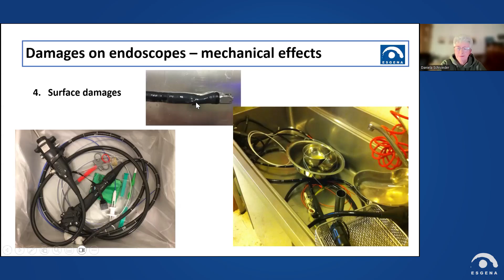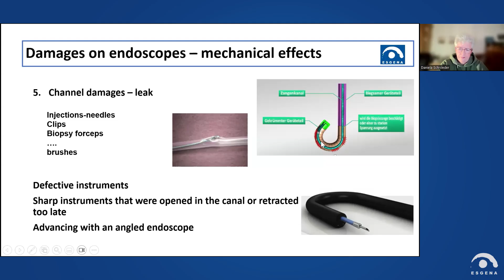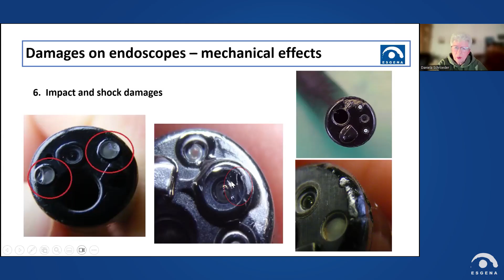Channel damages, which can cause a leak due to defective instruments. For example, we once had a production batch of brushes. They were kinked really soon, and then by withdrawing, they perforated the entire working channel. Sharp instruments that were opened too early or retracted too late, or advanced by pushing with force against the resistance of the angled endoscope, can cause damages and leaks. Even with shock or impact damages, here you can see that we have some broken parts on it. Even this endoscope will work properly. Maybe you have some cracks or some scratches on the screen, but it will still work properly.